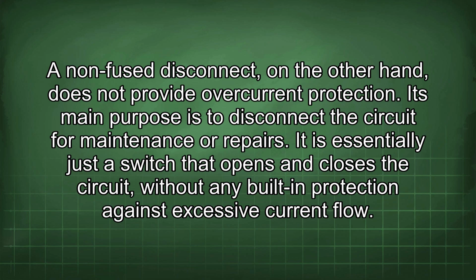A non-fused disconnect, on the other hand, does not provide overcurrent protection. Its main purpose is to disconnect the circuit for maintenance or repairs. It is essentially just a switch that opens and closes the circuit without any built-in protection against excessive current flow.